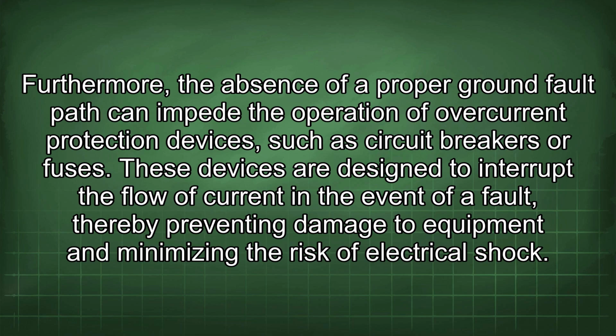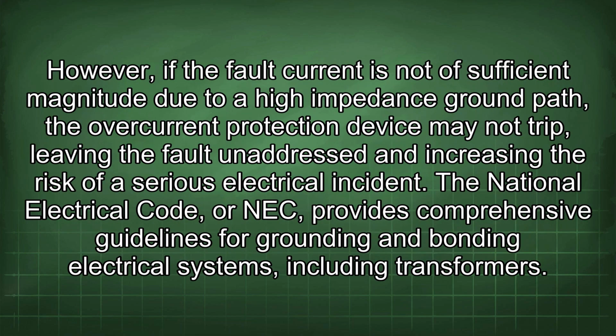Furthermore, the absence of a proper ground fault path can impede the operation of overcurrent protection devices, such as circuit breakers or fuses. These devices are designed to interrupt the flow of current in the event of a fault, thereby preventing damage to equipment and minimizing the risk of electrical shock. However, if the fault current is not of sufficient magnitude due to a high impedance ground path, the overcurrent protection device may not trip, leaving the fault unaddressed and increasing the risk of a serious electrical incident.